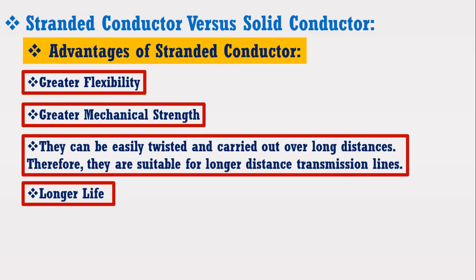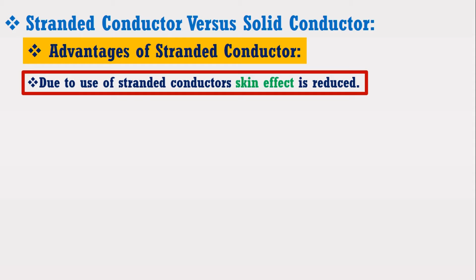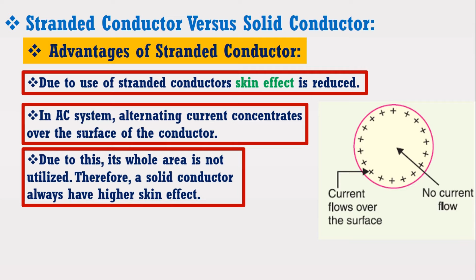Now I am going to discuss the most important advantage of a stranded conductor. Due to the use of stranded conductor, skin effect is reduced in the overhead transmission line. Now one may be confused about how skin effect is related to a stranded conductor. The answer is that in an AC system, alternating current concentrates over the surface of the conductor. Due to this, its whole area is not utilized. Therefore, a solid conductor always has higher skin effect. On the other hand, in a stranded conductor, the whole conductor is divided into small wires of small area. Due to this, the area of the individual wires is small as compared to the area of the solid conductor.